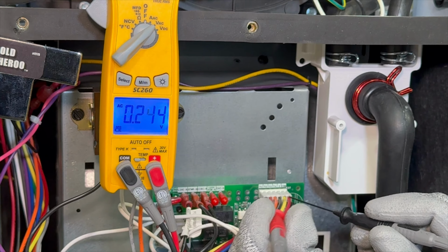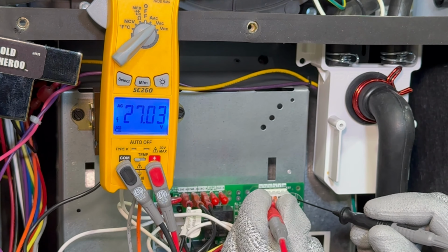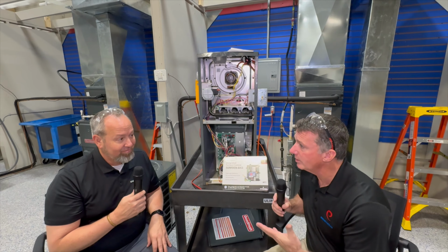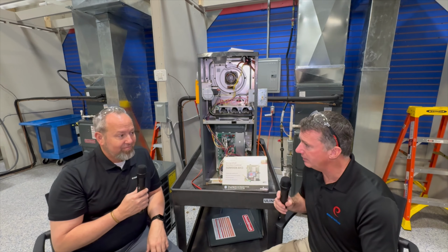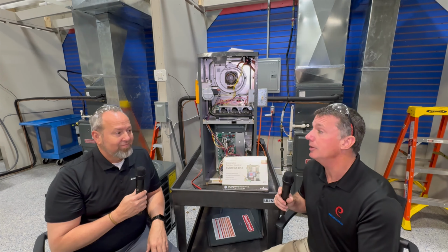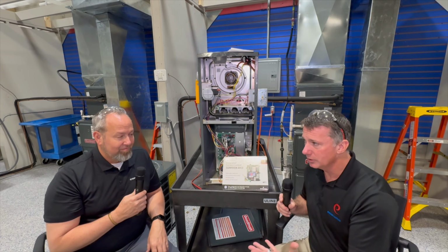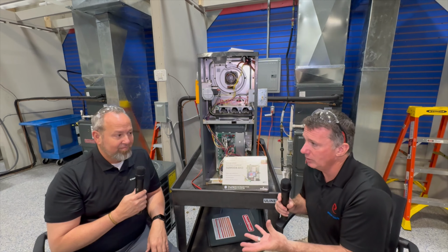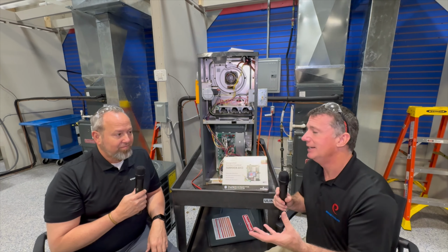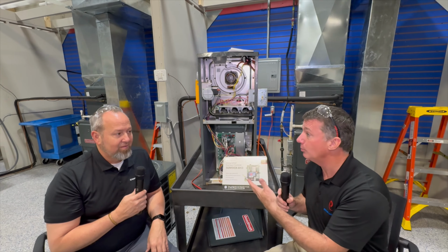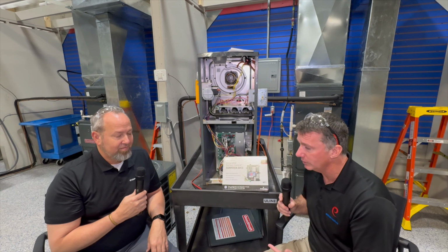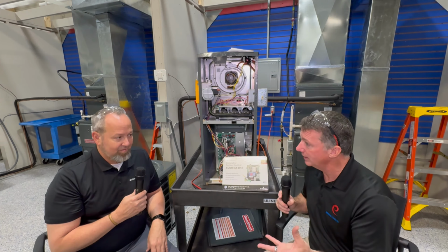So you can have a combination of both, but we can now utilize a board that can function with either one of those signals. And when we were talking to Regal Rexnord about that, it was because many of the equipment manufacturers needed to decide how they were going to program. Our motors from the manufacturer aren't programmed. It's not until we get to the equipment manufacturer that they design the ramp profiles and the programming for it. So some are using the 24 volt AC, some are using the pulse width modulated DC voltage.